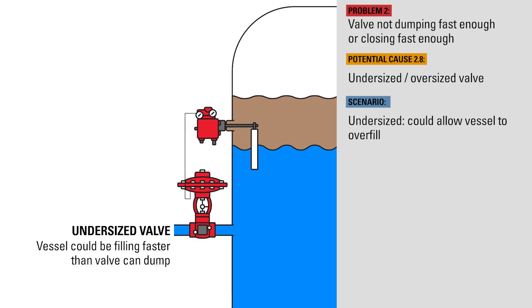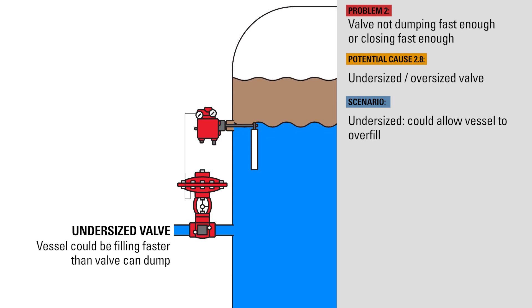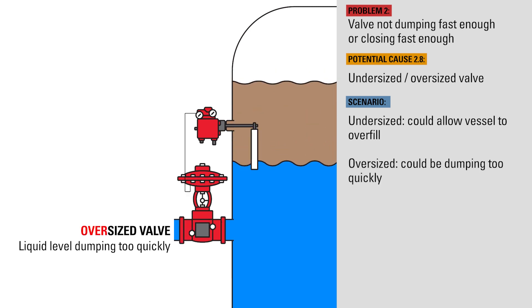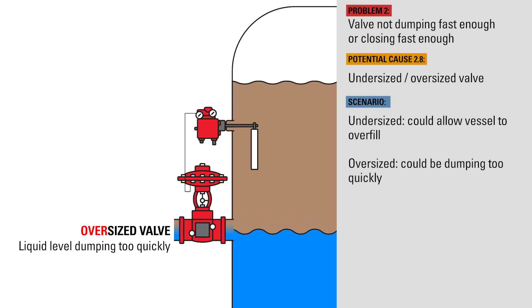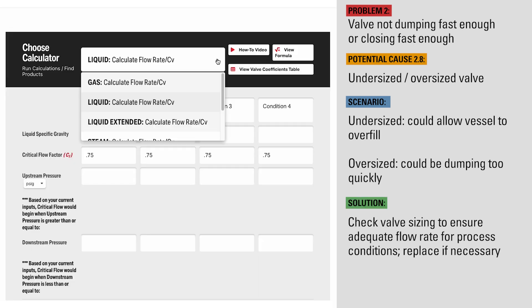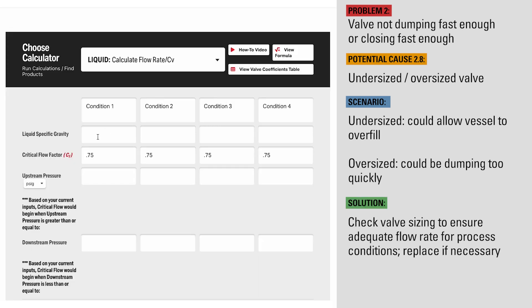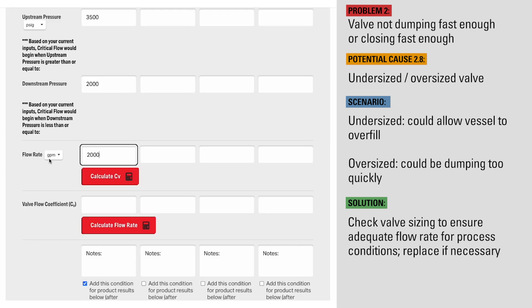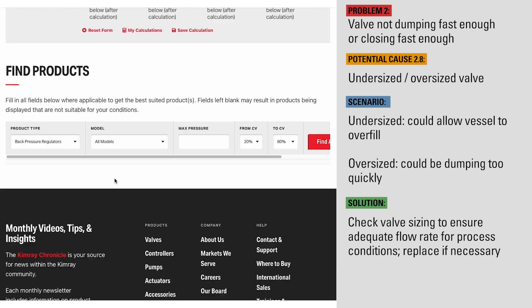An undersized valve could allow the vessel to overfill because it can't dump the liquid fast enough. An oversized valve could be dumping too quickly, not giving adequate time for the actuator to fully close the valve before the liquid falls below a critical level. Double check the sizing of the valve to ensure adequate flow rate for process conditions, and replace the valve if necessary.